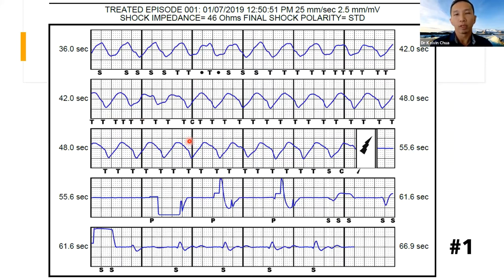The device appropriately detected this and delivered a shock to it. The key to this strip is why did the device detect it even though this was just 130 beats per minute? This was actually due to several areas of double counting. You can see this double counting, sometimes even triple counting of each QRS, led to detection. So even though this was actually double counting, it led to an appropriate and effective shock, even though this VT was way below the detection zone.